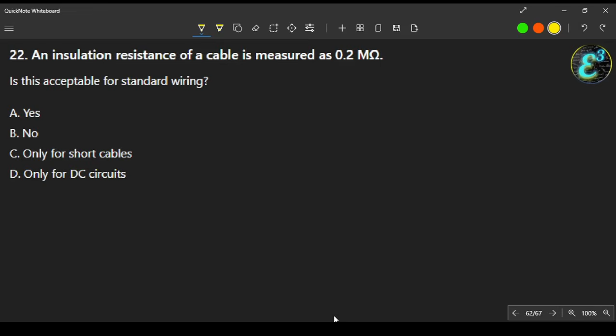Next, an insulation resistance for cables is measured at 0.2 mega ohms. Is this acceptable for standard wiring? Earlier we established that the acceptable value is 1 mega ohm. Since this is less than 1 mega ohm, the answer is no, it is unacceptable.